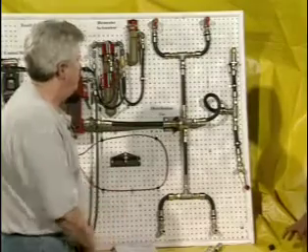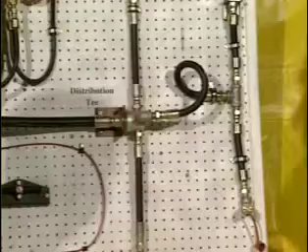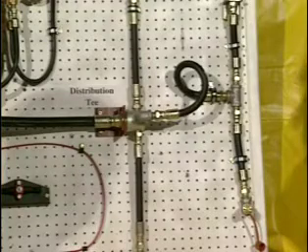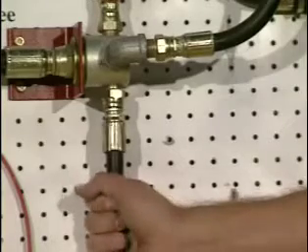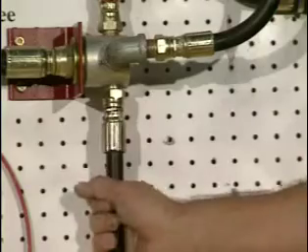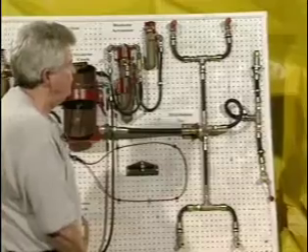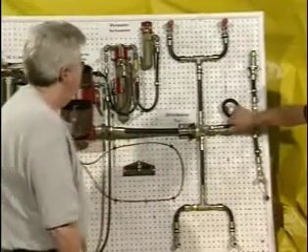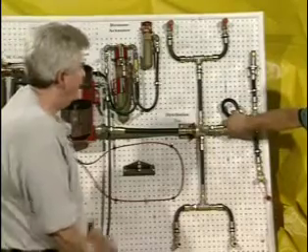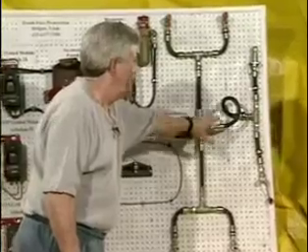Okay. But you have those limitations on these systems, which, if you notice, I put a curl in this particular hose. You can wrap that hose to make up the difference to give you your 3 to 1. You notice that the fittings that we're using on here are all swivel fittings. There's an O-ring. They feel loose if you go up there and feel them. I know inspectors are going to go up there and they can grab those and they'll move. Like this? Right. And they're going to think, oh, there's a problem there. There's not. There's an O-ring built inside of this that'll seal that. That's why we use the swivels.